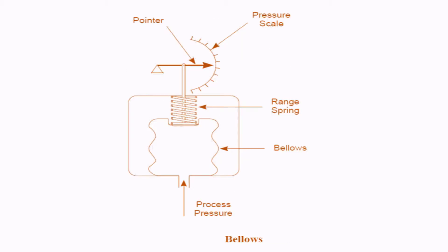Next we have the bellows type. A bellows pressure sensor looks like a small metal can with flexible sides, and a spring is attached to one end of the bellows. When pressure is applied from the bottom, the bellows expand and move the spring a distance that is proportional to the force. A pointer is attached to the spring and that indicates the pressure — this is how a bellows gauge works.